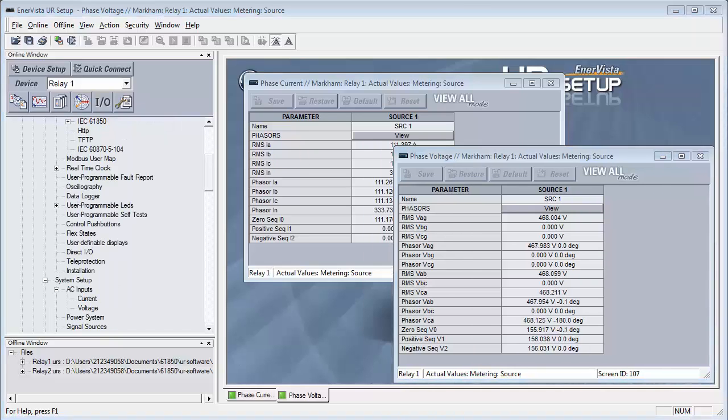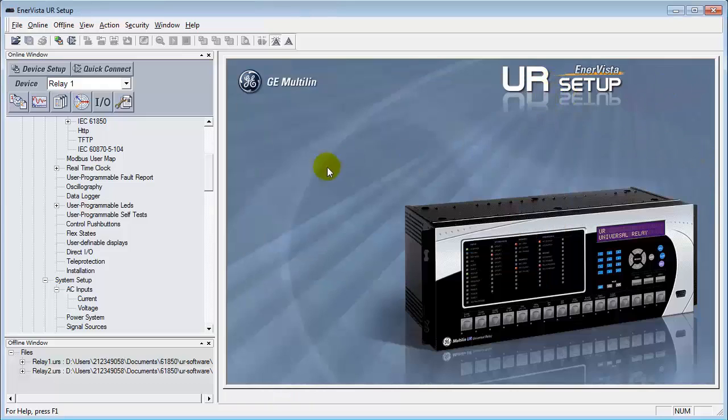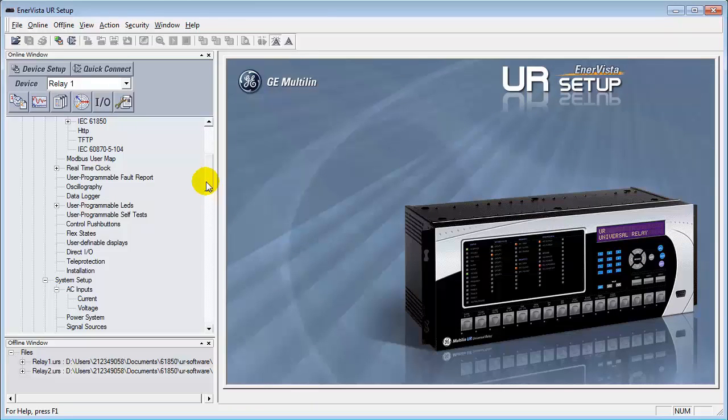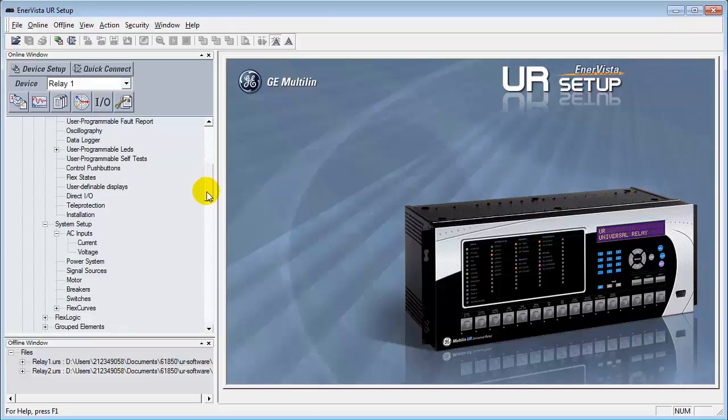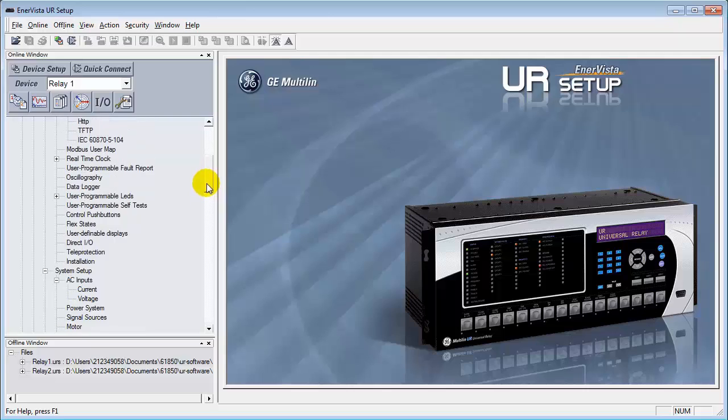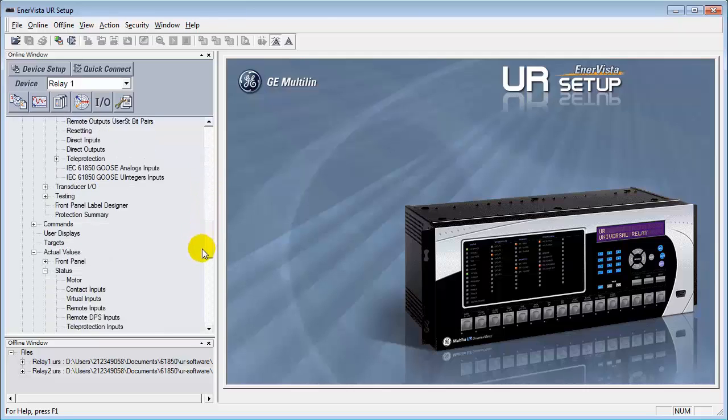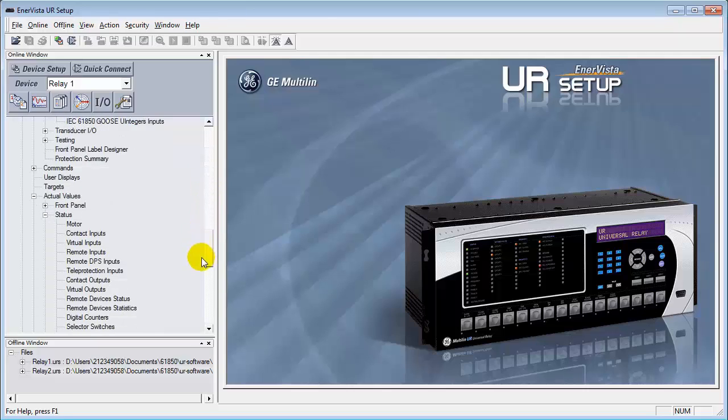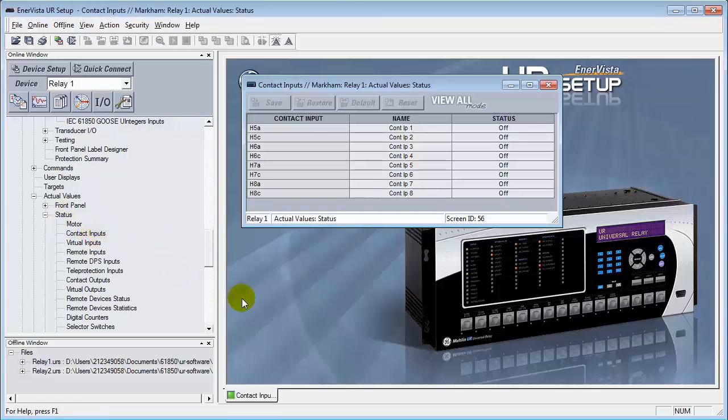Let's also check our contact inputs to confirm that their states are changing as well. Now that we've confirmed that the analog signals are working, let's verify the digital signals. So, with the aid of my colleague here, Antoine, we're going to verify that the digital inputs are working as well. The digital inputs are located under actual values. And under actual values, we're going to go down to status and then open up contact inputs.